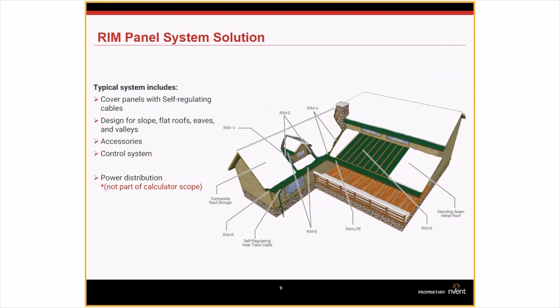For a RIM system, the roof and gutter calculator selects the appropriate eave panel based on roof style and slope, and provides a matching valley panel where needed. A cable cover completes the system with a seamless metal plate over the entire heating cable. The amount of heating cable, connection kits, and accessories are all provided in a full bill of material, with breaker size and quantity noted separately for the customer to supply.